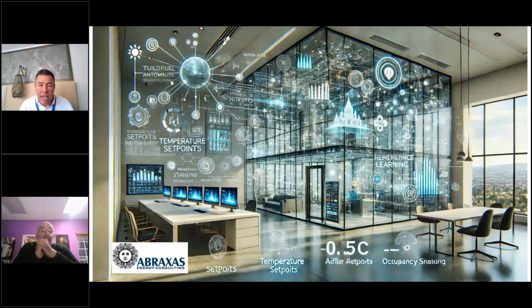What we're doing with all of this data that goes into the cloud is comparing it against other trend log data sets, comparing the exact condition of all the points of monitoring and control in the system. Then we compare those to conditions that maybe generated an alarm event, or that through calculation or our algorithm are running inefficiently. So the autonomous sequence of controls we still do at the field level is now being done in the cloud, but with much larger data sets.